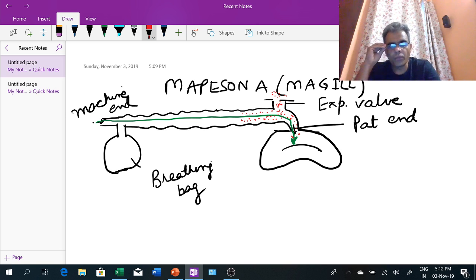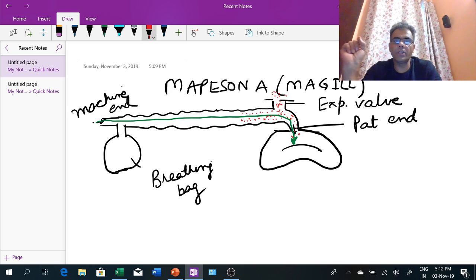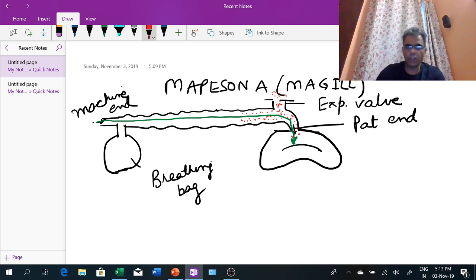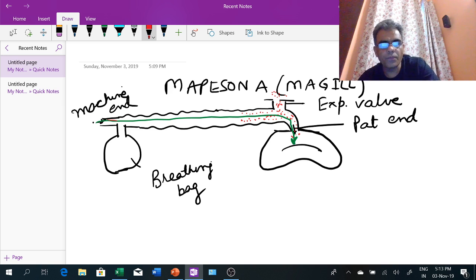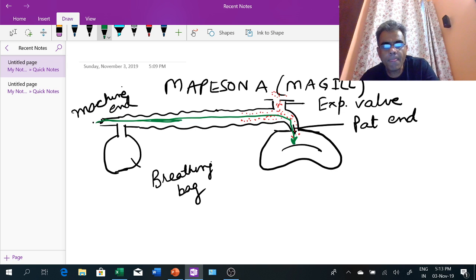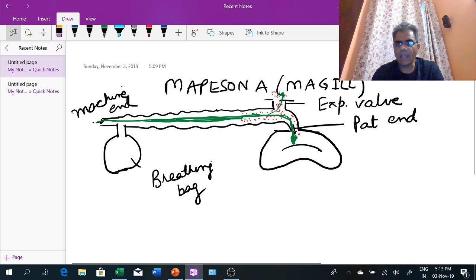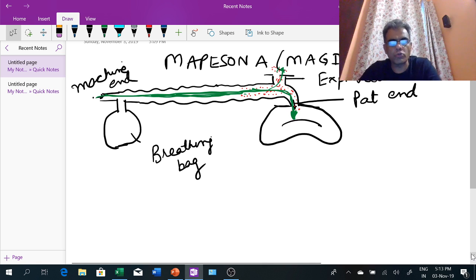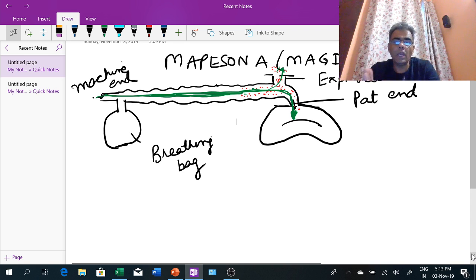The aim of every circuit is that there should not be any re-breathing. To prevent re-breathing, fresh gas flow is defined — the flow coming from the anesthesia machine. There should be sufficient fresh gas flow to push the expiratory gas out through the expiratory valve and deliver fresh gas to the patient. For every circuit a specific fresh gas flow is defined to prevent re-breathing.